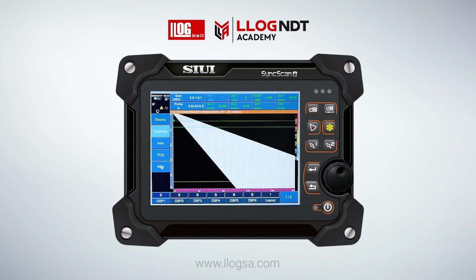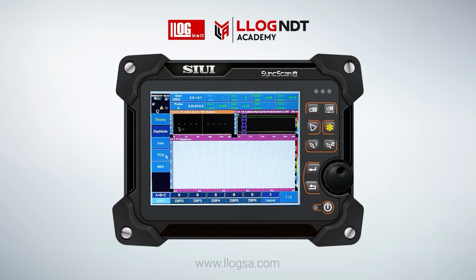Now we will activate the weld profile previously created in the Scan Wizard. Within the Display menu, under the INDN option, enable Groove Display. Finally, configure the screen layout. In the Display Mode option, select Display 1 from the submenu. Here, choose A plus B plus C, which corresponds to the scan views. The pre-scan settings are complete. We are now ready to start scanning using the encoder.